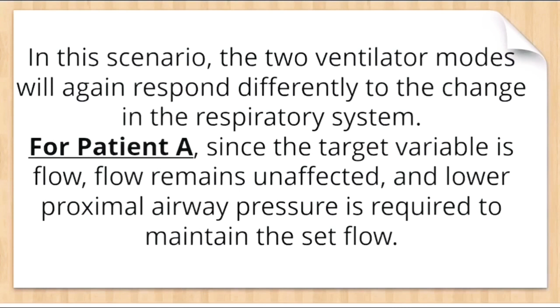Now if there are sustained inspiratory efforts, what will happen? Alveolar pressure is going to decrease. With this, if the patient is on flow targeted mode, that is patient A, the flow is constant. It will not change. But what has to change is the proximal airway pressure. In order to keep this flow constant, the proximal airway pressure will decrease. That is the reason that in case of sustained inspiratory efforts, if the patient is on flow targeted mode, you can see the decrease in the proximal airway pressure on the ventilator.